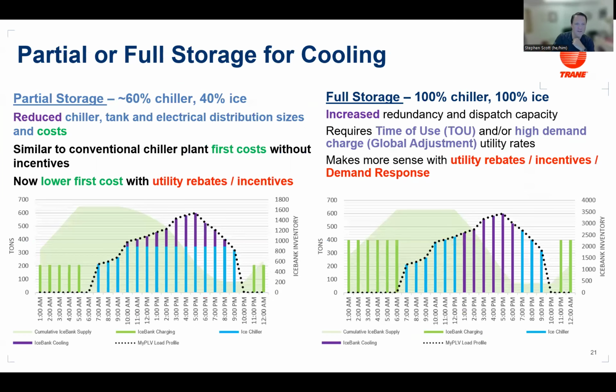The next slide is really two ways of doing it. On the left is partial storage. Roughly, if you think of say 100 tons or 100 kilowatts of energy, the partial would be the chiller takes up 60% of it, 40% is roughly ice storage. So then what it does is reduce the size of the chiller you'd normally install in the building, and reduce the electrical size needed in your chiller plant, freeing up electricity for other things.